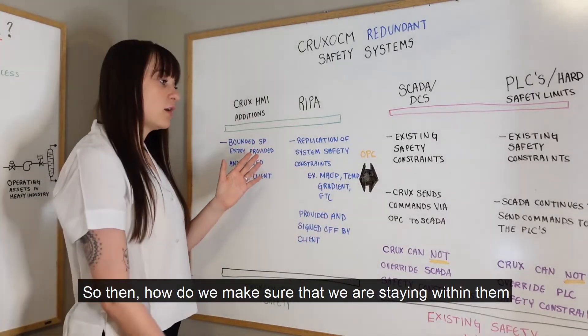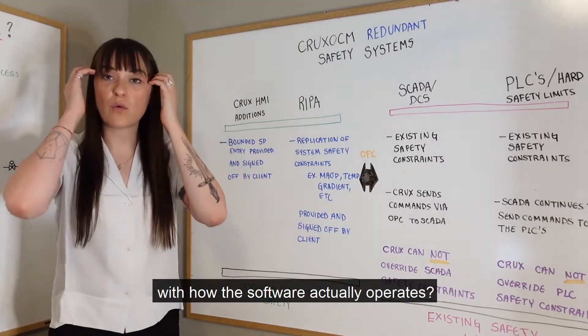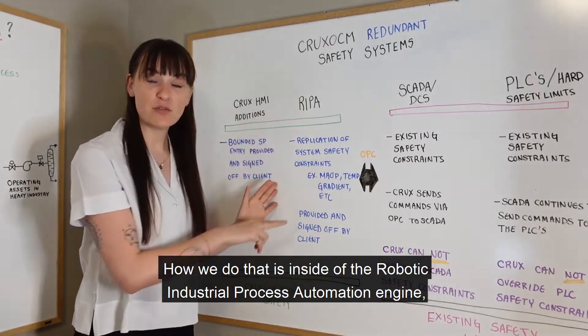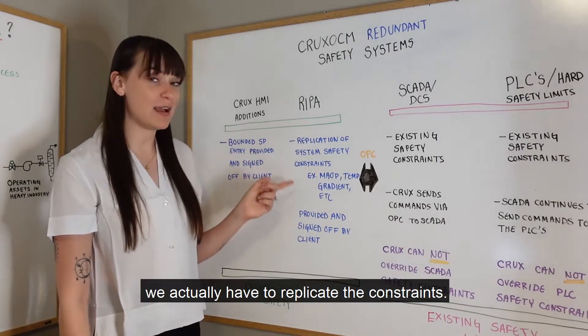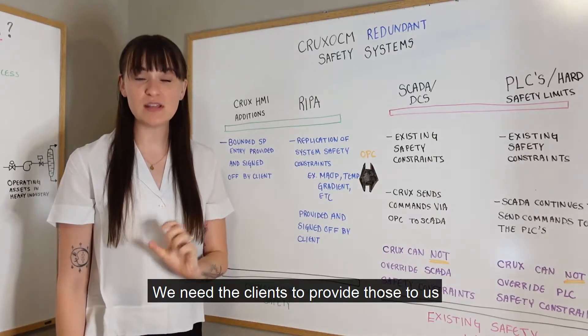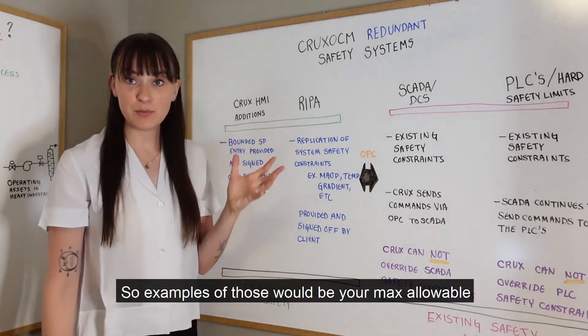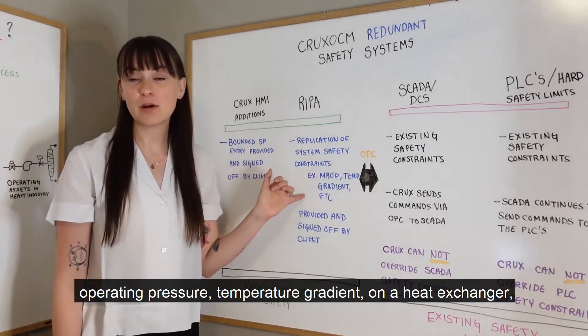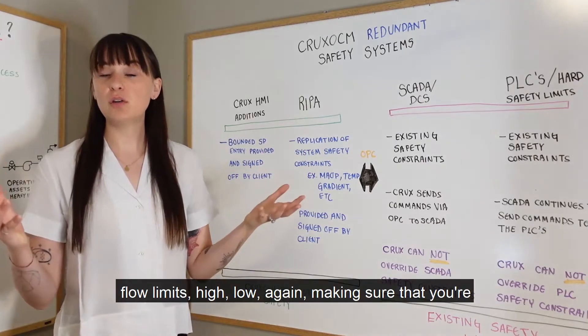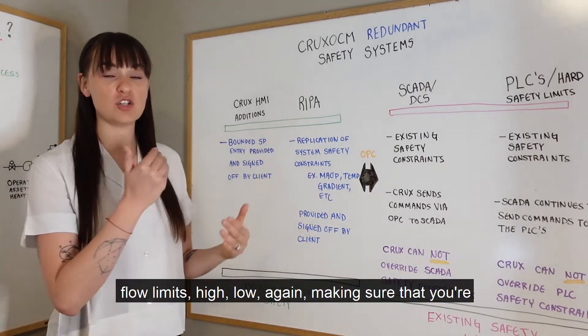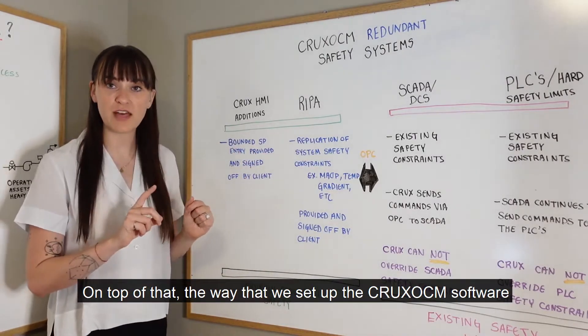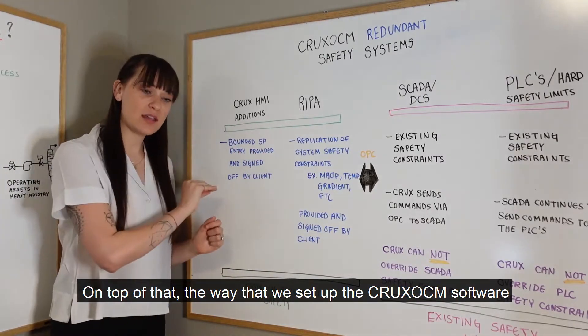To make sure we stay within those constraints in how the software actually operates: inside the robotic industrial process automation engine, we replicate the constraints. We need the client to provide those to us and sign off that they are correct. Examples include maximum allowable operating pressure, temperature gradient on a heat exchanger, and flow limits — high and low — ensuring you're well within the bounds of safe operation.